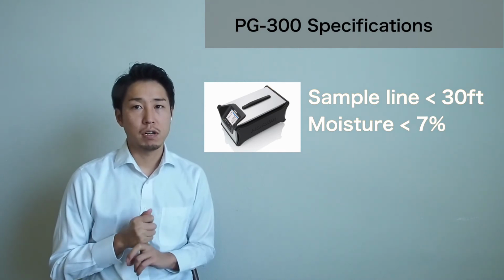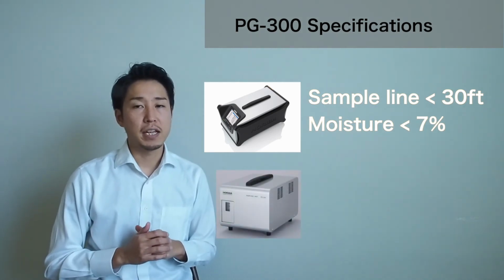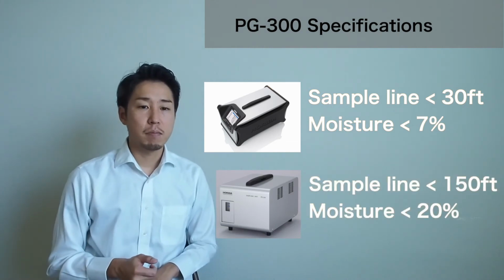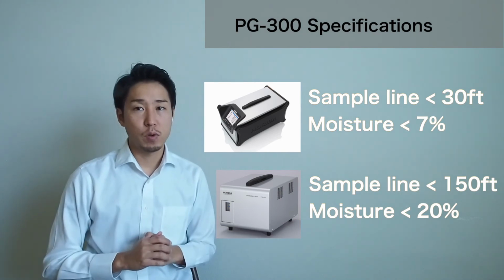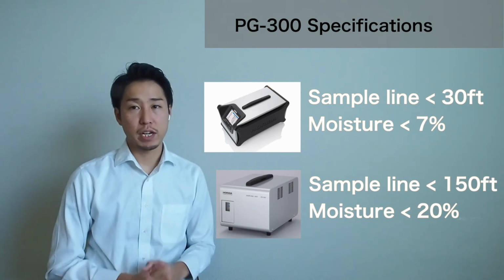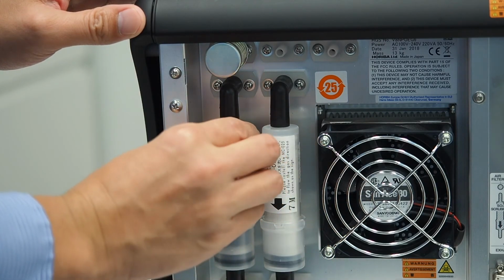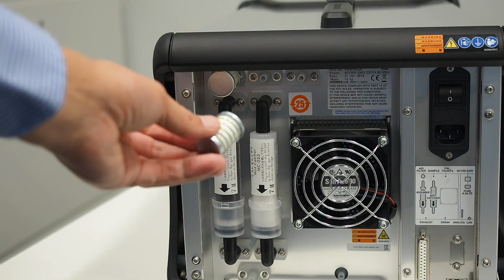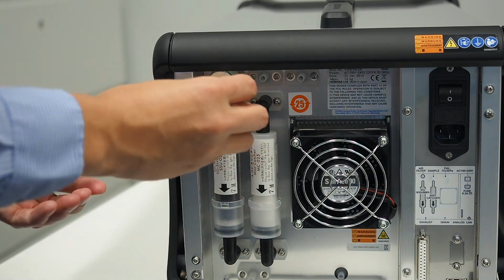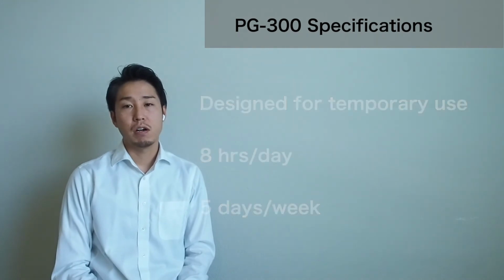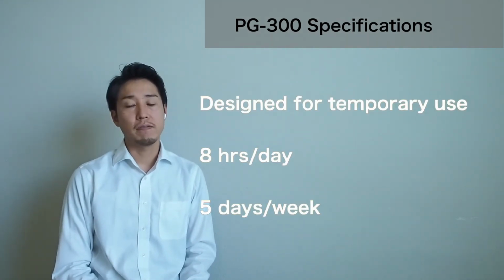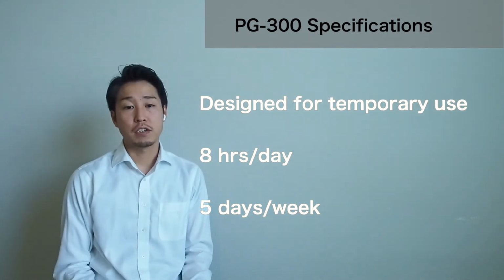Let's summarize the spec of the PG. Remember, for the PG300, the sample line length needs to be less than 30 foot, and the moisture level needs to be lower than 7%. If the condition is above that number, you will need the PS300. The PS300 spec is that the sample line length needs to be less than 150 foot, and the moisture level needs to be lower than 20%. PG has only 3 consumable parts. See the back side. These are the mist catcher, the scrubber, and the air filter. Customers can replace the mist catcher and scrubber every 3 months and the air filter every 2 weeks. This is based on the assumption you use PG for 8 hours a day and 5 days a week. But you don't know how many hours you have actually used them for.